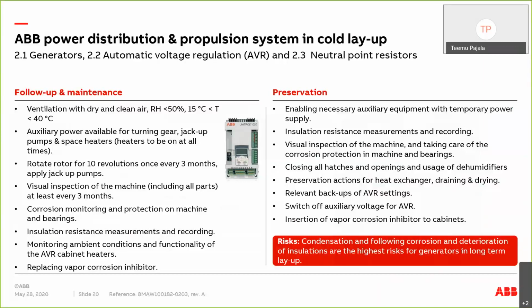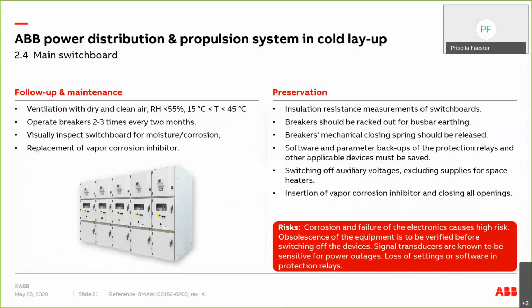For AVR, especially for Unitrol and new types of equipment where we have computers, it's good to take backups of all the settings and software to make sure that whenever we need to restart the system, we have the latest parameters available, so that we don't need to start the recommissioning again. And then auxiliary power can be switched off for AVRs. Main switchboard.